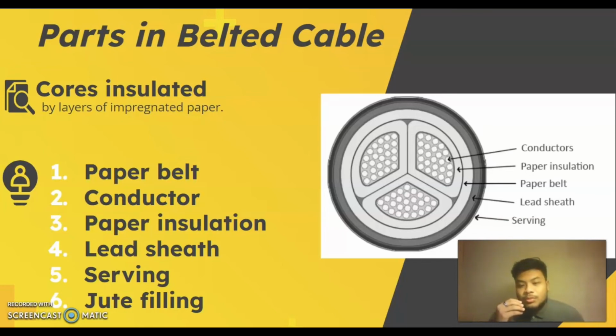And to protect the cable from moisture and mechanical damage, the belt is coated with lead sheath, and one or more layers of armoring with the outer serving cover the lead sheath. So that's all for parts in belted cable.